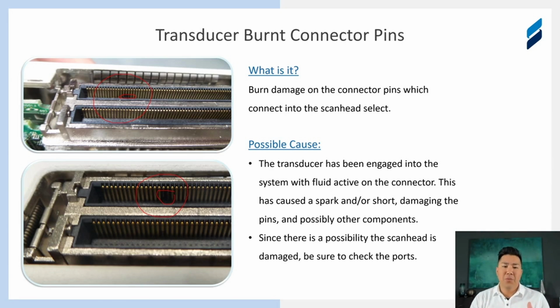Now, when they short, it can be something as simple as a repair that would replace the connector of this transducer. That's on the really optimistic side. But again, these circuits go all the way down to the crystal, and this can actually blow up the crystal on the other end. So this is something to keep an eye out for, keeping these things dry. Another cause is just a loose connector on the port, where the pins are close enough and it happens. That doesn't happen very often. We typically see more of it around unnecessary fluid sitting there on the transducer, and this can wreak havoc.